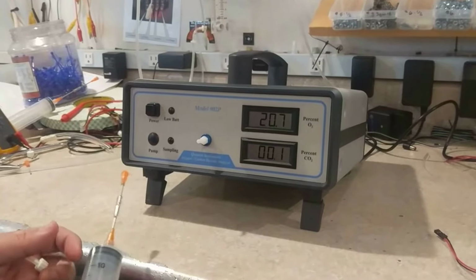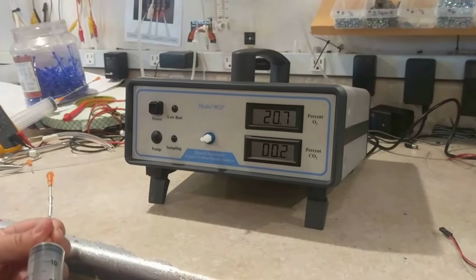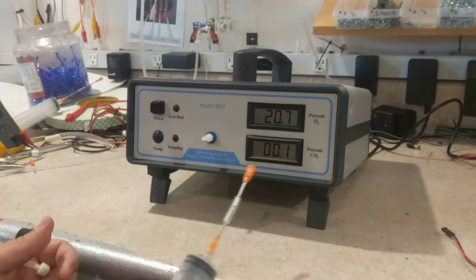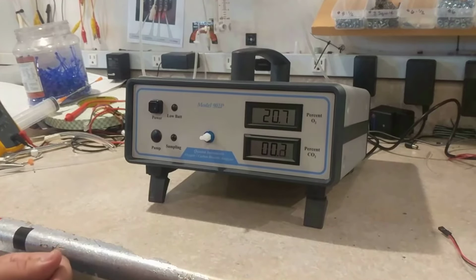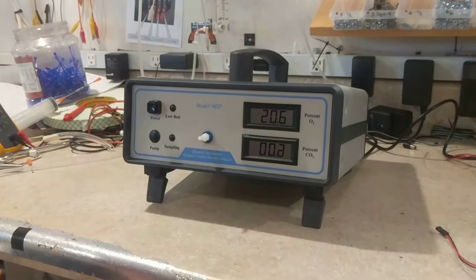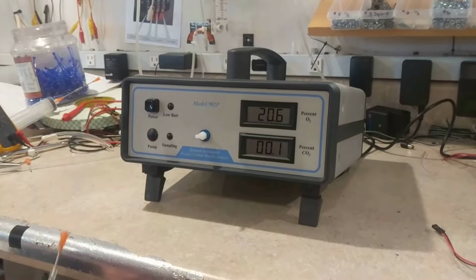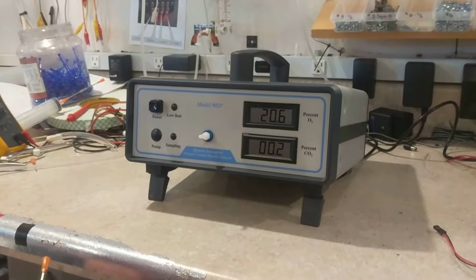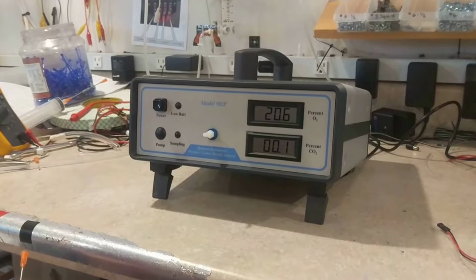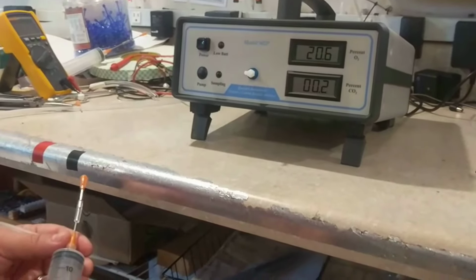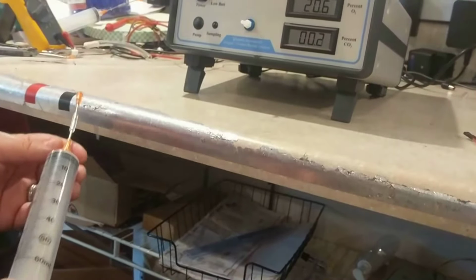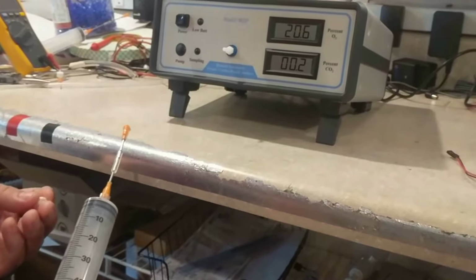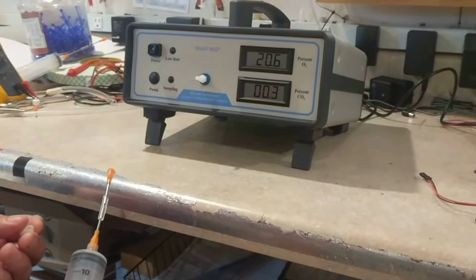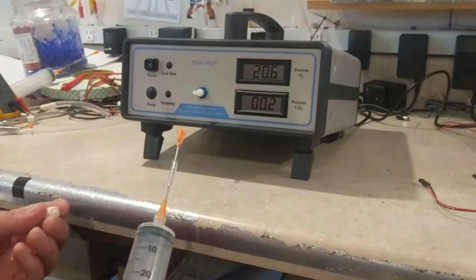So today we're going to be performing a quick calibration check on an instrument that has a CO2 sensor. This would be a useful method to use if the only thing you have is pure CO2 and you aren't sure if the instrument is out of calibration, or maybe someone has adjusted the CO2 span on the back of the instrument and hasn't communicated that fact.